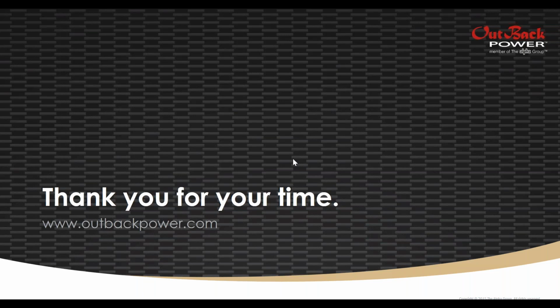George asked if we can change the SkyBox in software from 60 hertz to 50 hertz. George, the answer is it sure looks like it at the moment, but no, we've turned that off. That's something we may be able to do in the future. We certainly have the hooks and the brains to be able to do it. Whether or not we're allowed to from a regulatory and nationally recognized testing lab point of view is a different issue. So today we've turned off all of the ability to adjust frequency within SkyBox. The only thing that you as a qualified installer can adjust are grid interconnection ride-throughs where appropriate. So you can set it for PREPA standards instead of California Rule 21 standards, for example.